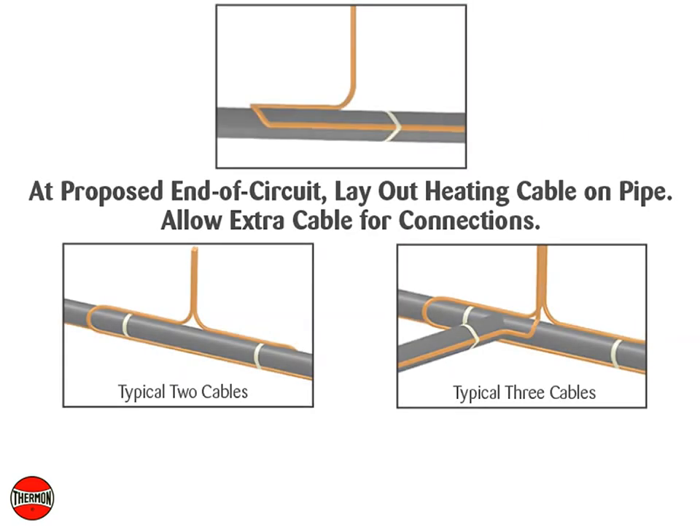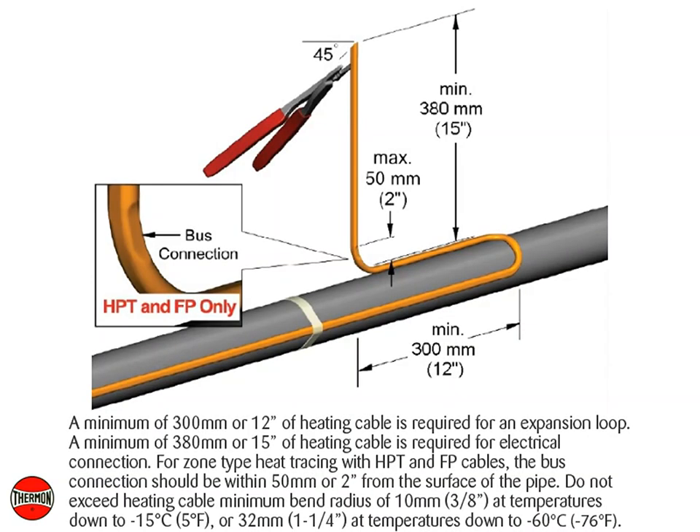At the proposed end of circuit location, lay out heating cable on pipe, allowing extra cable for the power connections. A minimum of 300 millimeters or 12 inches of heating cable is required for an expansion loop. A minimum of 380 millimeters or 15 inches is required for electrical connection. For zone type heat tracing with HPT and FP cables, the bus connection should be within 50 millimeters or 2 inches from the surface of the pipe.